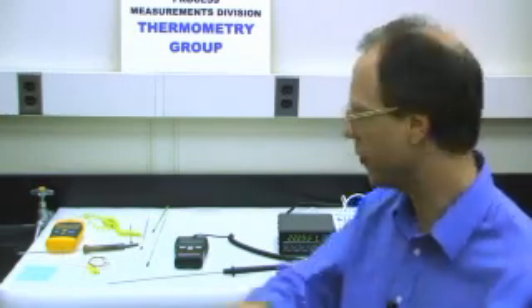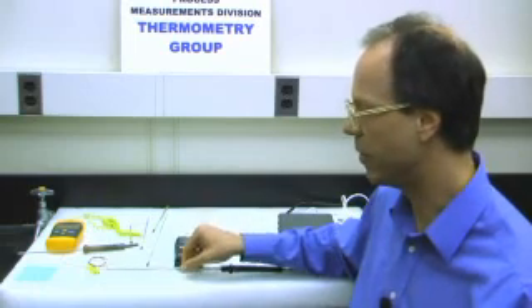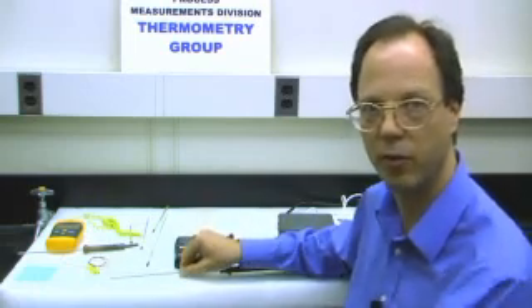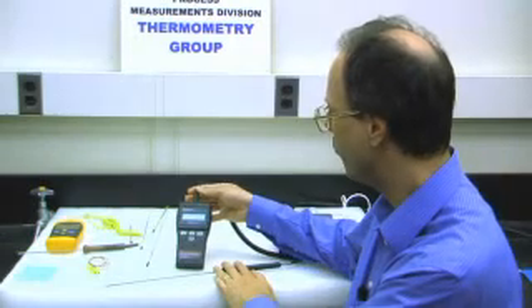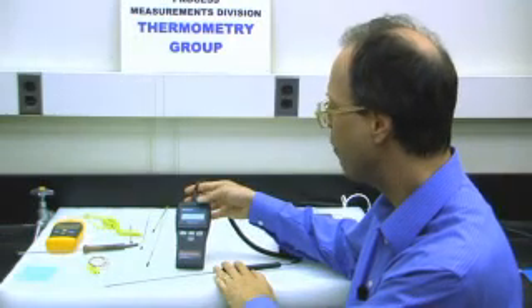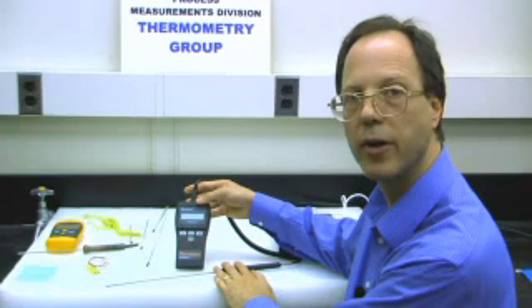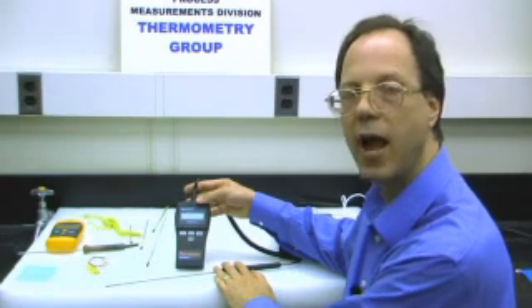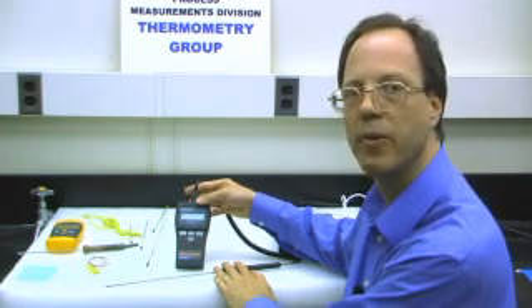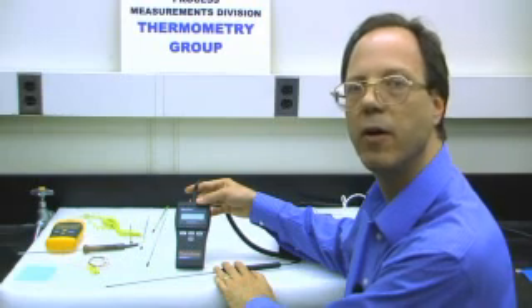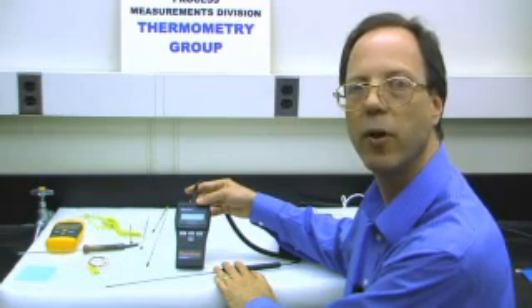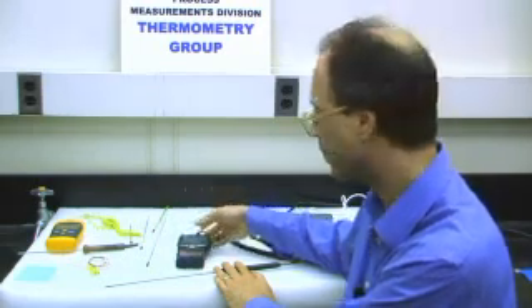Let me talk now a little bit about good measurement practice. Number one, I've already talked about it, avoid shock. With the electronic thermometers, you don't want to drop them on the table or even worse, onto the floor. This readout has a removable probe. Often the readout and the probe are calibrated together. Unless you're absolutely certain that a probe is interchangeable with another probe, don't take the probe out and put a new one in. You'll get the wrong answer.